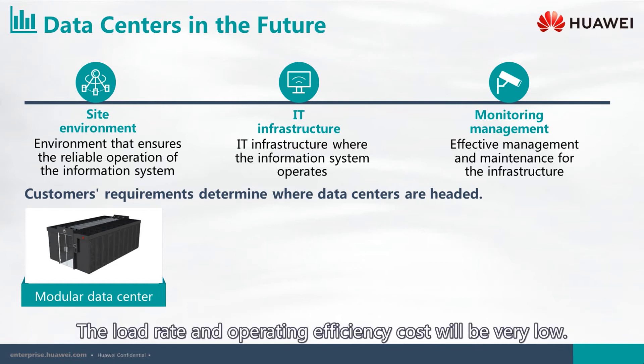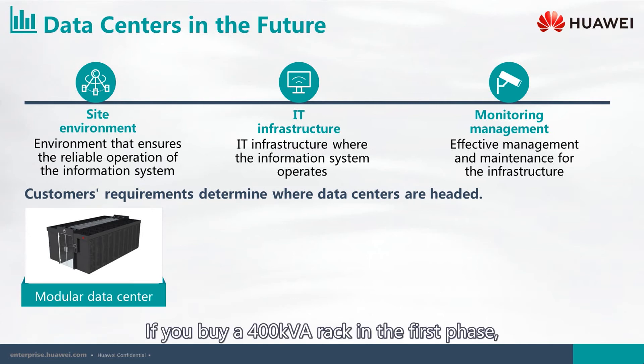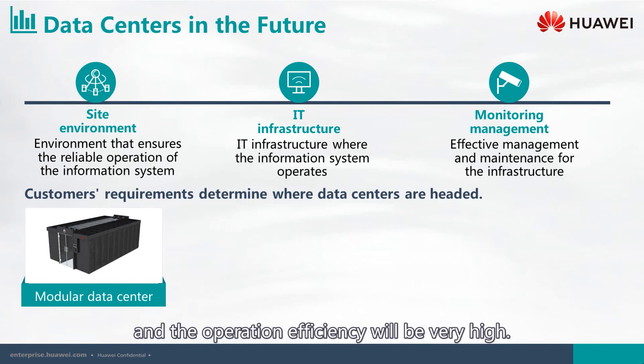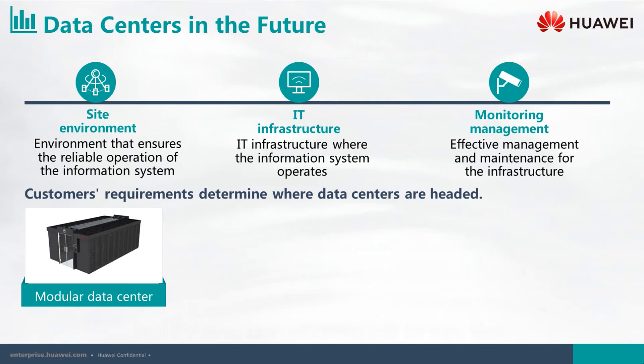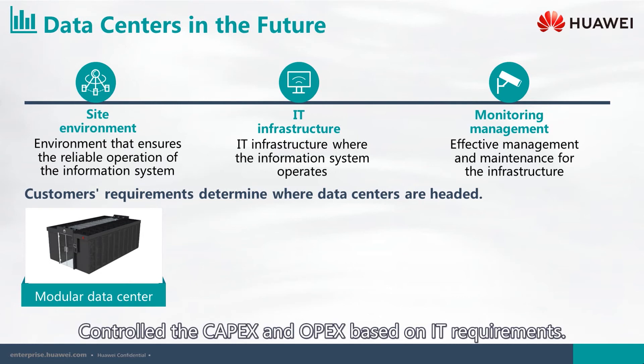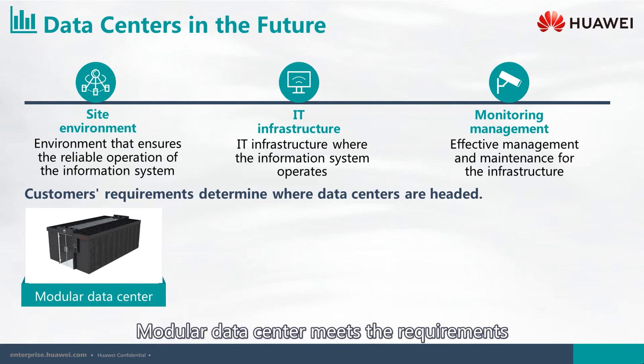With a non-modular approach, the load rate and operating efficiency cost will be very low. If you buy a 400 kilovolt-ampere rack in the first phase, you only buy four power modules — the combined power of those four modules is 200 kilovolt-amperes and the operation efficiency will be very high. The initial investment is called capex; the operational cost is called opex. Control the capex and opex based on IT requirements.